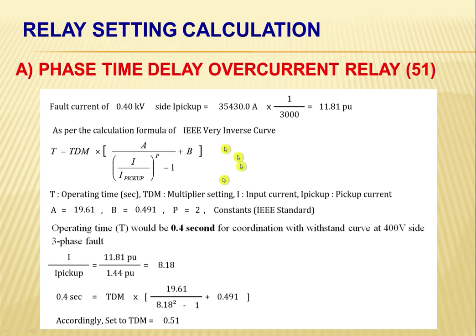Okay, so here is the formula to calculate our multiplier setting, or the time dial multiplier in ANSI terminology. This is a standard formula whether you are using the IEEE curve or the IEC curve. So this is for the operating time, which is equal to the multiplier setting. These are the constant values, A, B, and P. And I stands for input current, and this one is the pickup current.